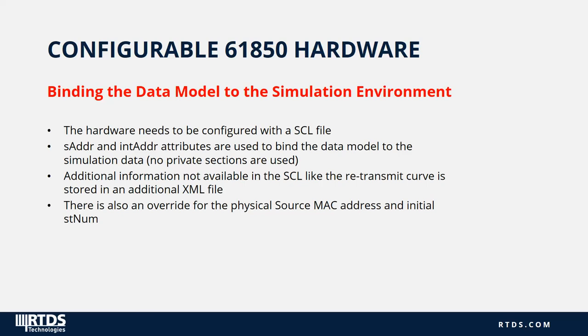Binding the data model to the simulation environment. The hardware needs to be configured with an SCL file. The sAddr and intAddr attributes are used to bind the data model to the simulation data, so no private sections are used. Additional information that is not available in the SCL file, like the retransmit curve, is stored in an additional XML file. Inside this additional XML file, there is also an override to substitute the physical source MAC address and change the initial state number of the GOOSE message.